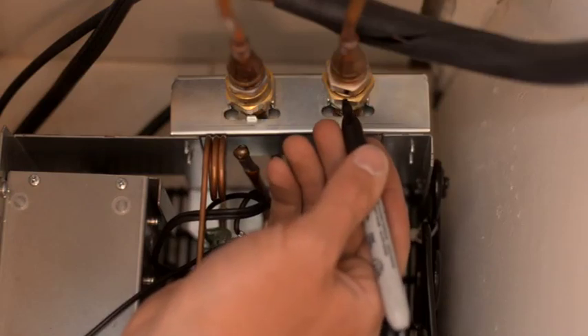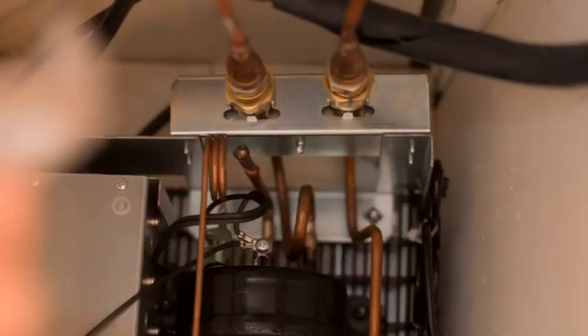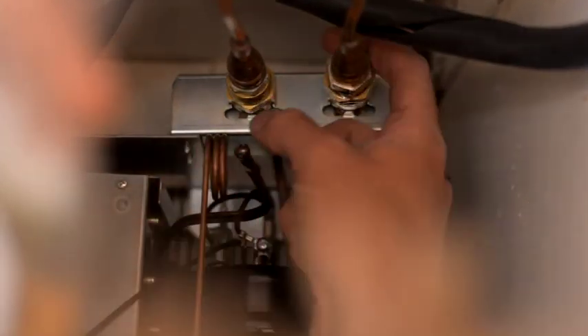Mark coupling with pen, then tighten additional one-sixth to one-quarter of a turn. Apply soap to couplings to ensure no leaks. Wipe soap off once verified.